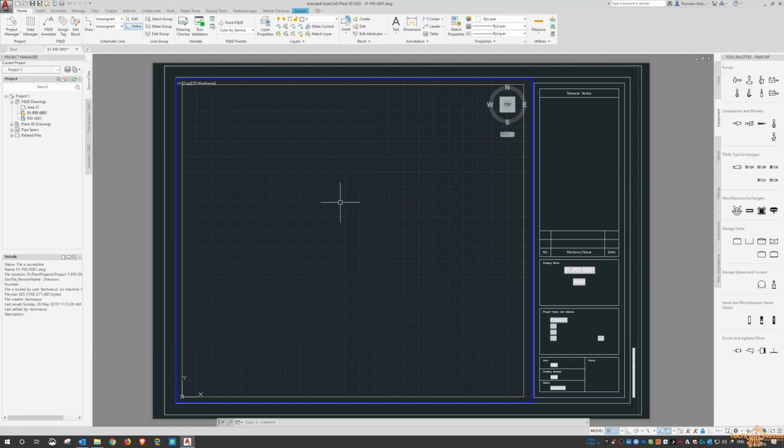Now, the P&IDs, traditionally, from when I used to do manual drafting, and then in the early days of CAD and working more and more with P&IDs, I was originally told when I was younger that the P&IDs usually flowed left to right. So in theory, you could cut the title blocks off and sticky tape all of the sheets together, and they will flow from left to right, showing the process. Obviously, there are going to be differences there where you might have a line that comes out of a tank and needs to go to a pump in another area of the project, and the lines won't necessarily line up. But from what I was told, they should always be considered to go left to right, so you would have all your inlets coming from the left and all the lines coming out on the right hand side. So you might want to take that into account when you lay out a project or a P&ID.